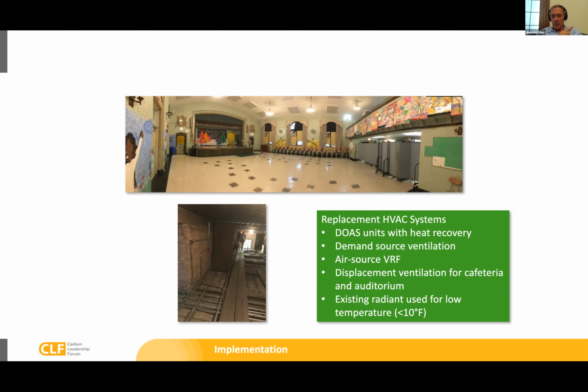I might add two benefits of displacement ventilation. One, by supplying fresh air low, you're getting the air into the breathing zone much more effectively. Right. And also by allowing the hot air to just rise and stratify, you are not cooling that upper layer of air to the same degree that you are the air in the people zone, if you will. And so it's more efficient from that perspective as well. Right.